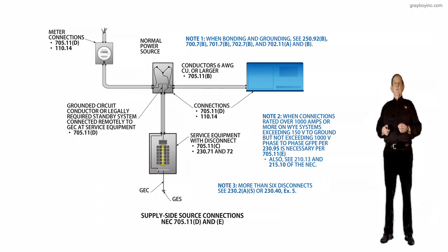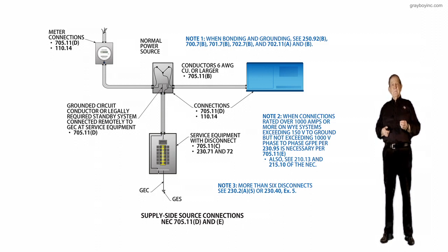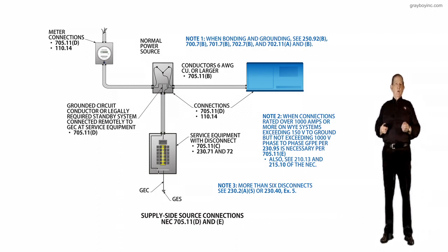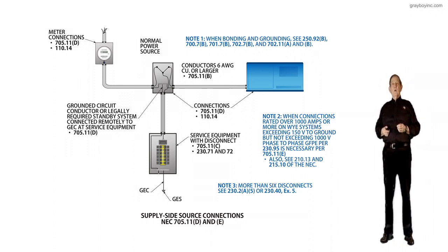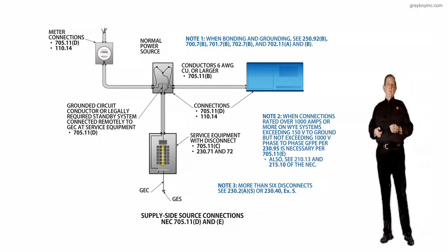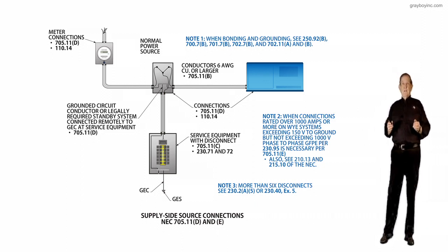And notice that the grounded conductor in the transfer switch you see there is tied in solidly, and we're not switching the grounded conductor. So that's maybe a three-pole transfer switch, as outlined in 250.30, informational notes one and two. So in other words, you could basically say you don't have to ground that generator because the generator, as you see, is grounded to that grounding electrode system at the service equipment with the disconnect, and it's also grounded back to the utility where it's earth grounded. So we find that the grounded conductor is not switched in this case.